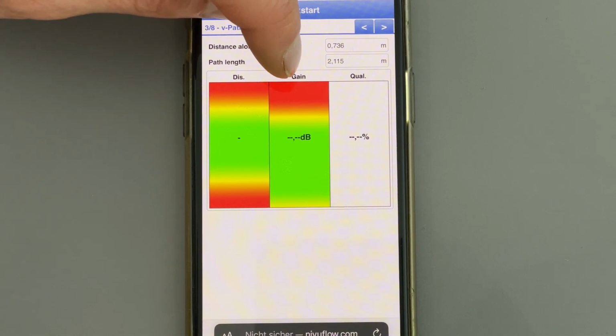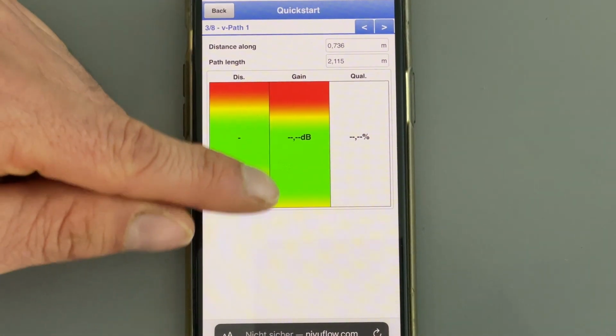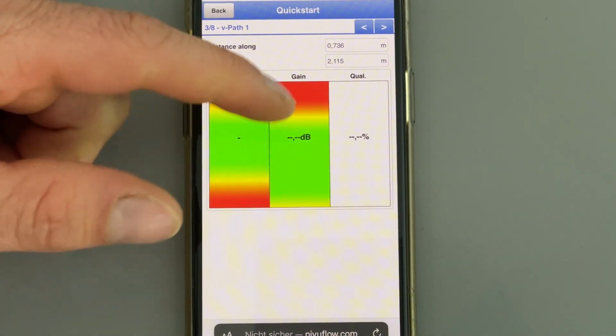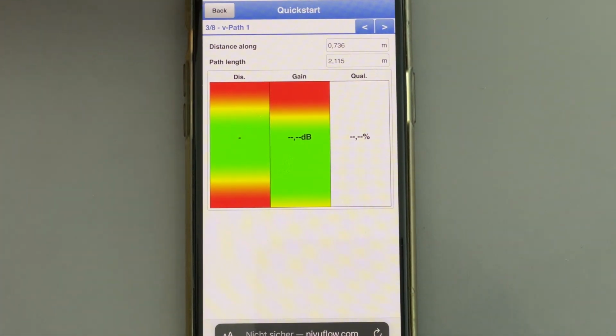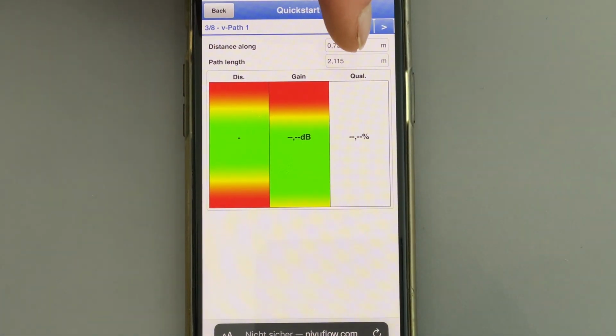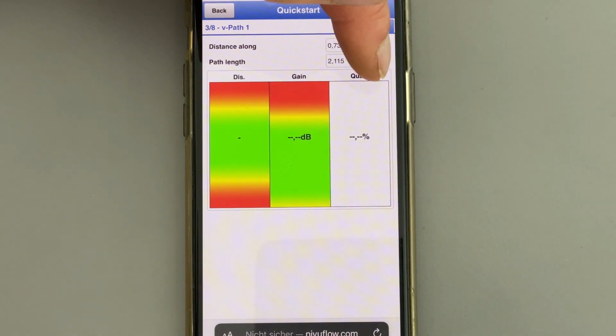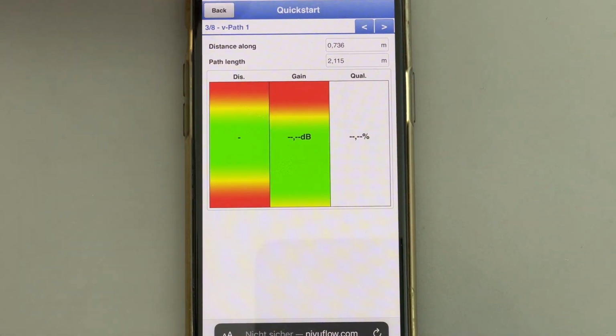The gain is for the amplification of the sensor, and should also be here only in the green area. If it's in the red, you're using too much gain, which is also not good for the sensor to work perfectly. And the quality is the quality of the signal received by the sensor. Also here it should be shown as a green bar. If it's red, you need to realign or find a new position for the sensors.